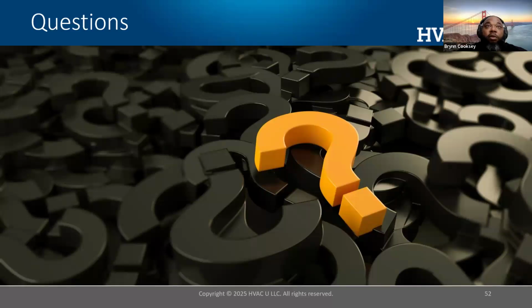So if we're going to do a heat pump retrofit, if I was going to come to your place, the first thing we would do is do a load calc. The load calculation per Manual J is going to have me evaluate your building shell. I put in physical features of your home, such as the dimensions, the volume, the type of insulation you have, how many people live there, how many pets, how many plants. We put a detailed survey of data into a software program and it gives us BTUs and tells us how big or small your heating and cooling system needs to be. If that process is skipped, nothing else will be right. So that's first and foremost.